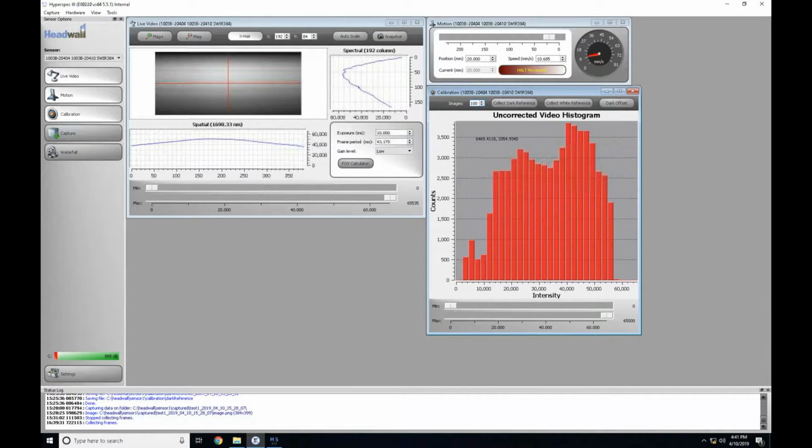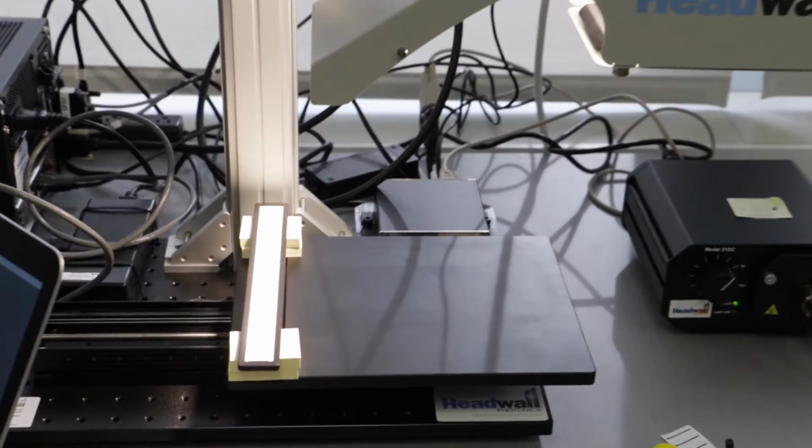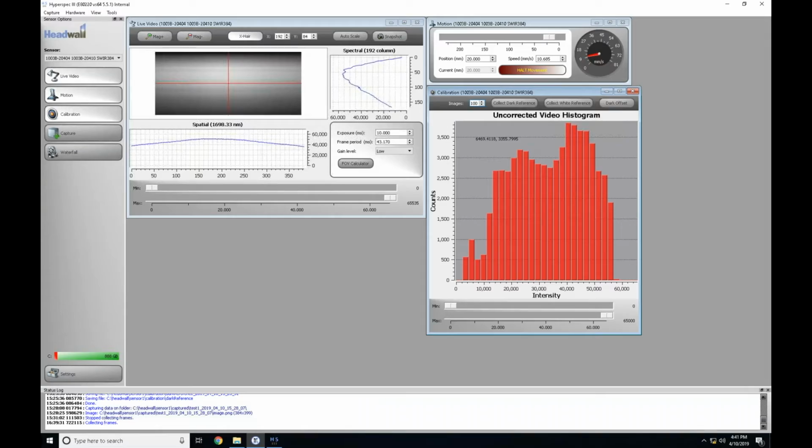It depends on a lot of things that aren't the sample. And all we care about is the sample. So the way, at least in a lab setting, that we calibrate that is right now I'm staring at a piece of Spectralon. And this piece of Spectralon has a very high reflectance across the whole spectral range. And I will gather what I call the white reference.